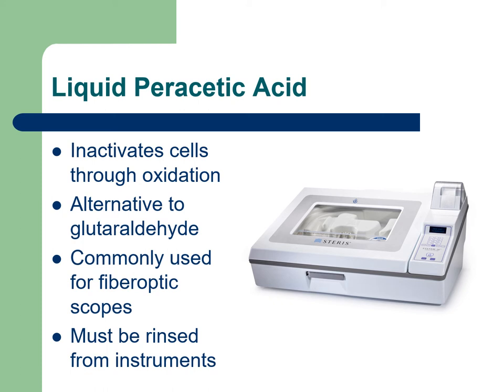We would put it in these big plastic bins, and you would soak the instruments in it, and after 20 minutes or so, you would get a high level of disinfection. But if you actually want to use it to sterilize, it takes hours and hours to sterilize with glutaraldehyde, and it is very caustic to the tissue, so it has to be rinsed methodically before it can come into contact with the patient's tissue.